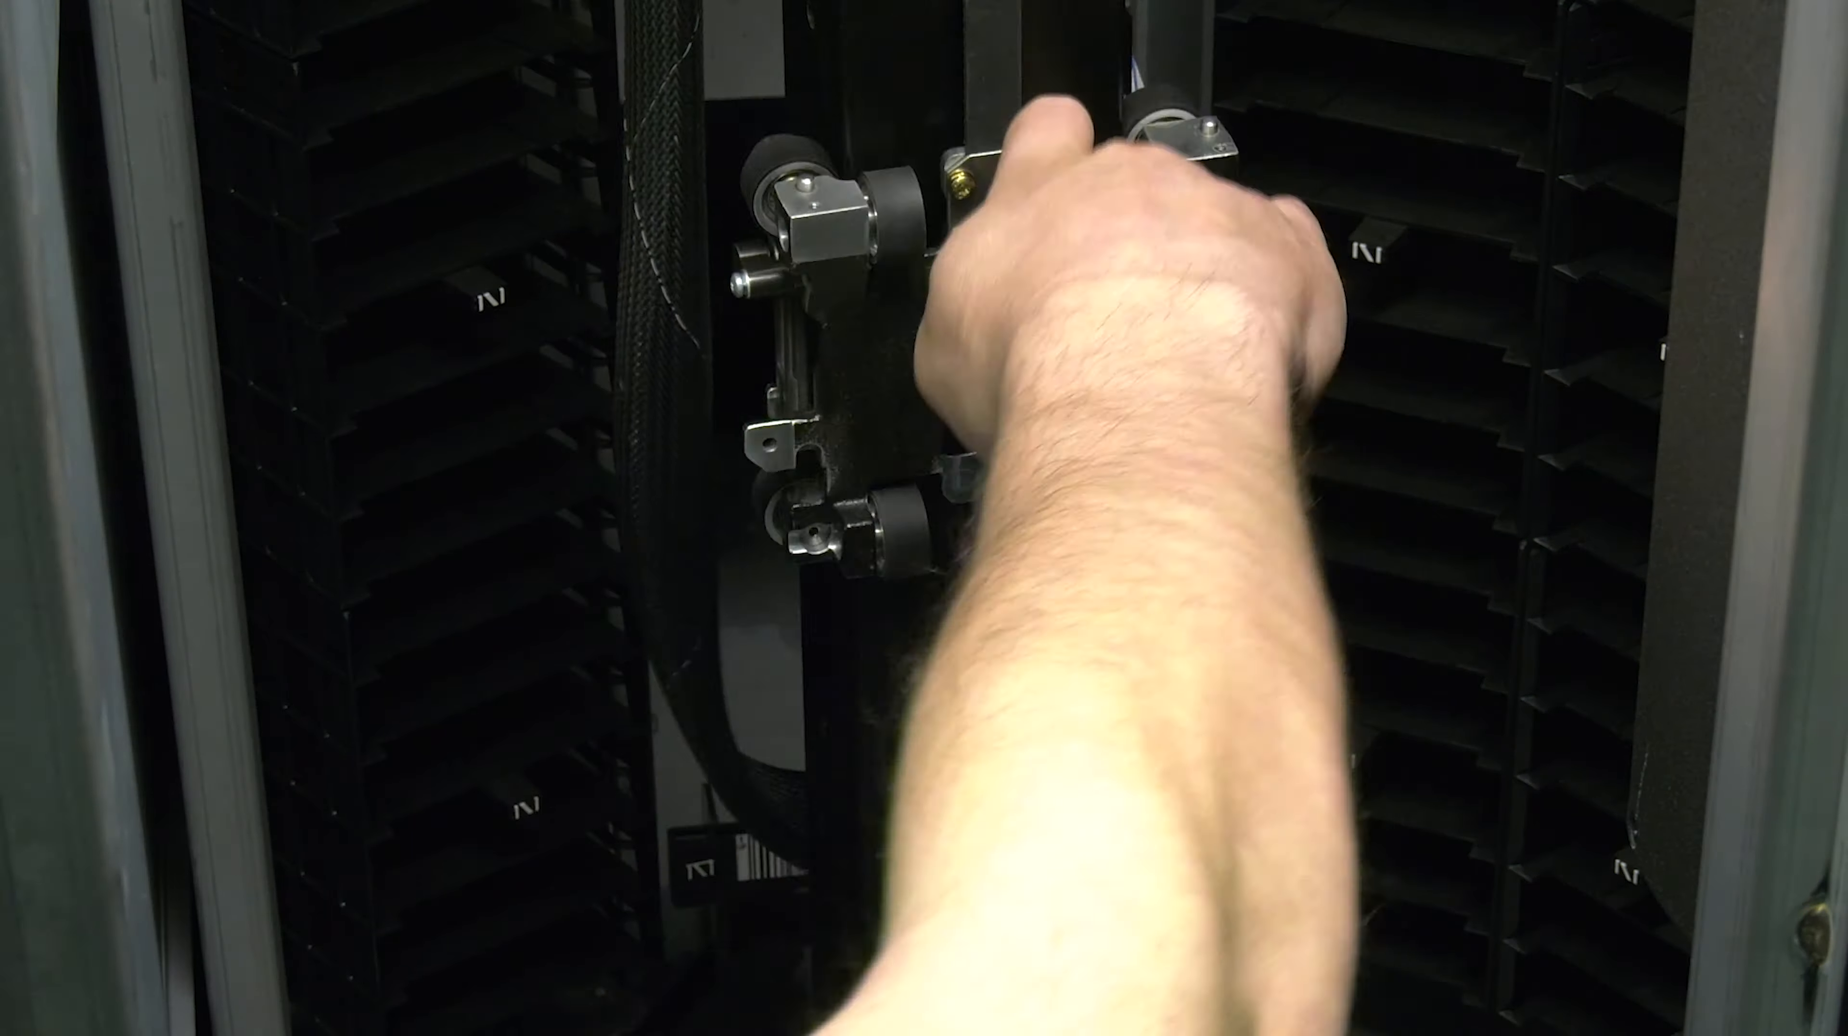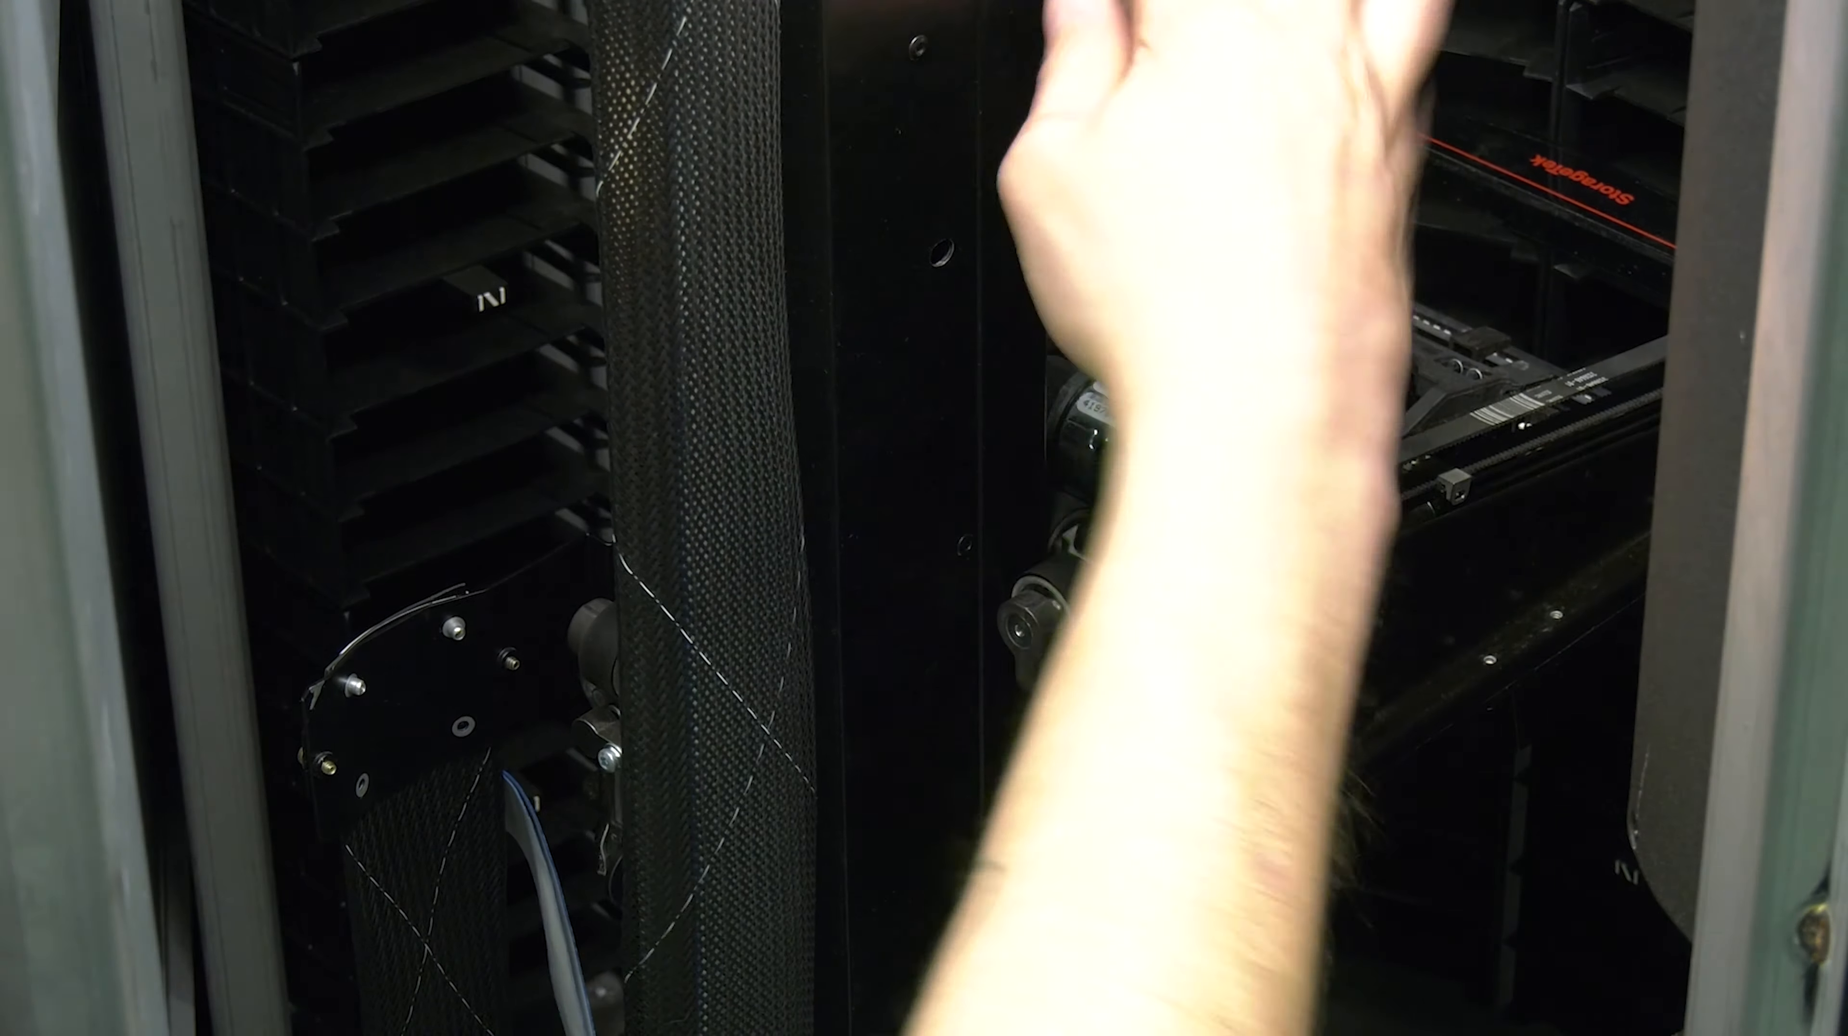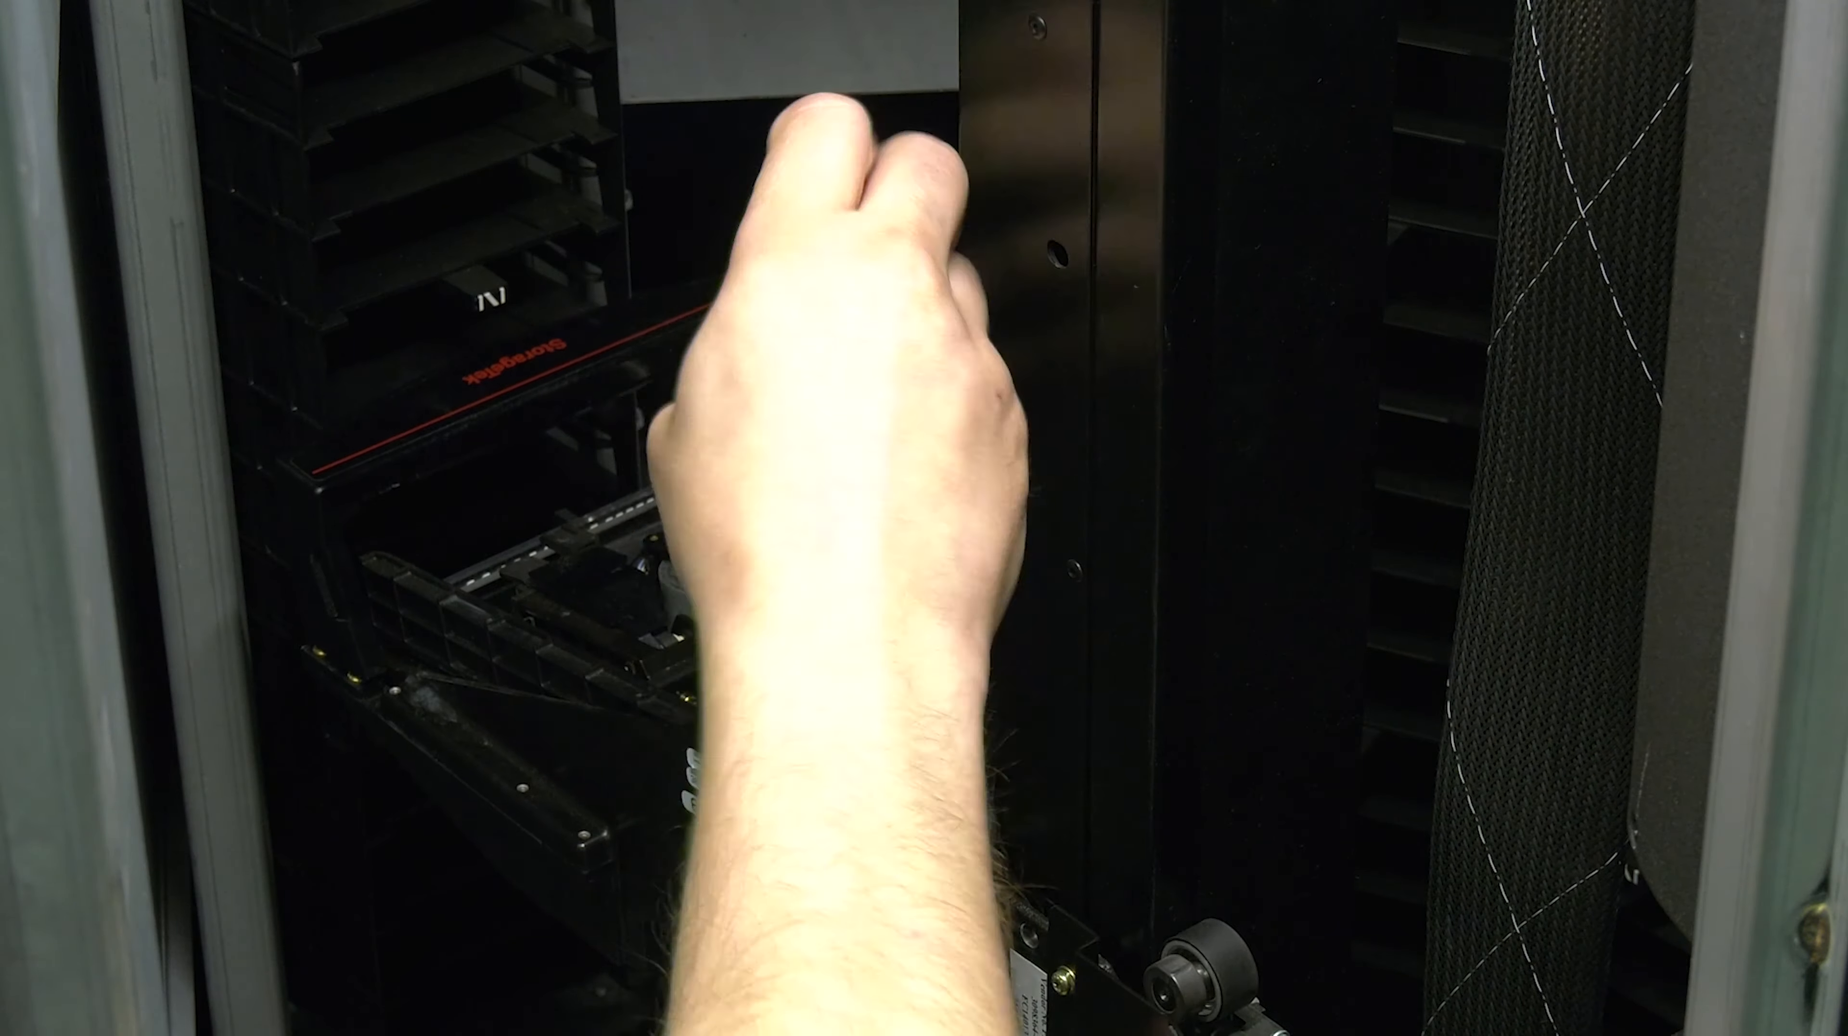You are now ready to install the replacement picker assembly. Carefully take the replacement picker and lower it into place on the vertical axis mount, ensuring that the two pins that hold the picker on the mount are in place in the two notches on the top of the picker. Then secure the picker to the mount with the four screws you removed earlier.